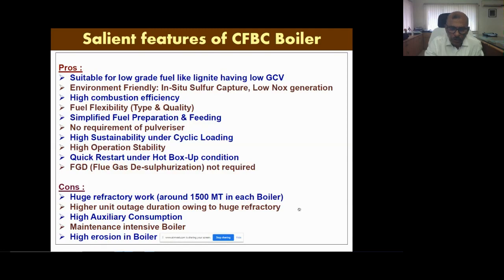Now, CFBC technology has a lot of advantages and some major disadvantages also. It is suitable for low grade fuel and good environmentally, as we capture sulfur. Low NOx generation is there because of the temperature, which we maintain at around 850, and secondary stage combustion gives high combustion efficiency, around 98%. Fuel flexibility means we are using lignite, but we have blended it with imported coal also. You can even use bagasse. Imported coal is 10 to 15%, so that variation is there.